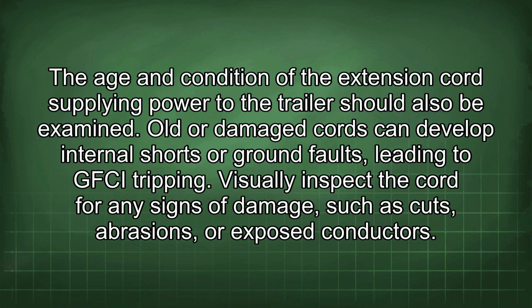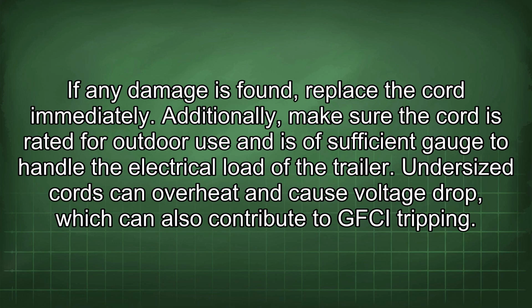The age and condition of the extension cords supplying power to the trailer should also be examined. Old or damaged cords can develop internal shorts or ground faults, leading to GFCI tripping. Visually inspect the cord for any signs of damage, such as cuts, abrasions, or exposed conductors. If any damage is found, replace the cord immediately. Additionally, make sure the cord is rated for outdoor use and is of sufficient gauge to handle the electrical load of the trailer. Undersized cords can overheat and cause voltage drop, which can also contribute to GFCI tripping.